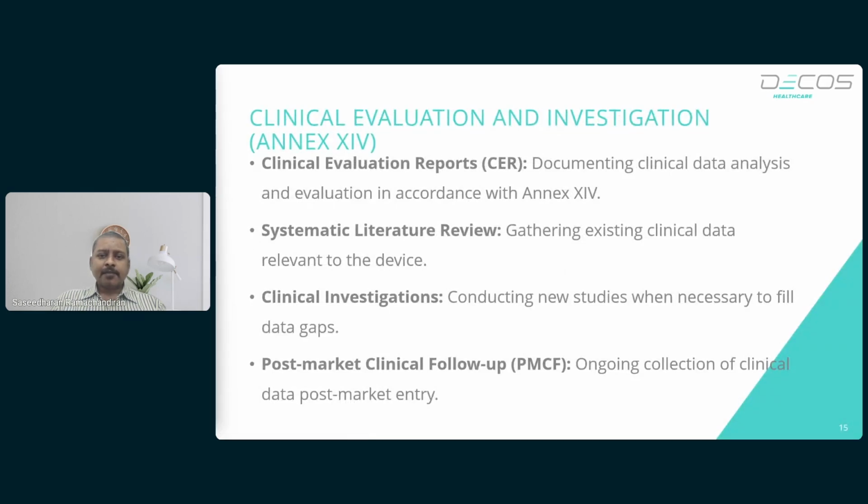Demonstrating device safety and performance requires comprehensive clinical data, like literature review, where the manufacturers gather relevant clinical data from existing sources to support safety claims. Clinical investigations, where, when existing data is insufficient, new studies are conducted to fill the gaps. Post-market clinical follow-up (PMCF) is required to continuously monitor device performance after it enters the market, ensuring the identification of any emerging risk.